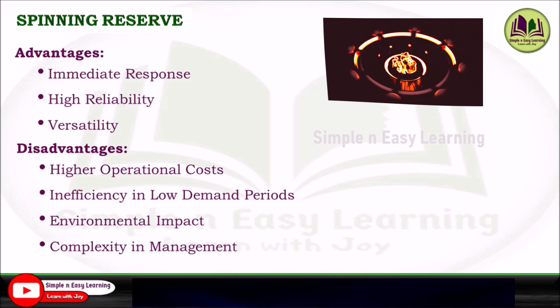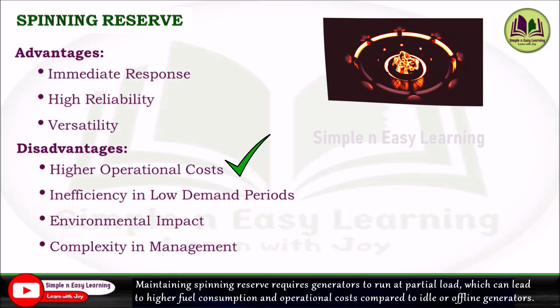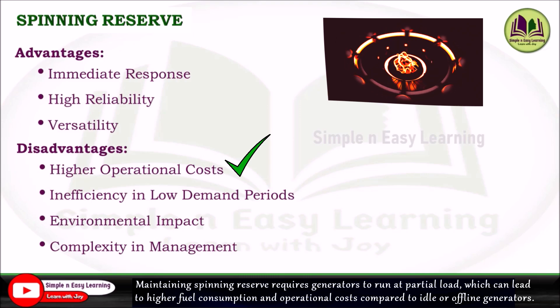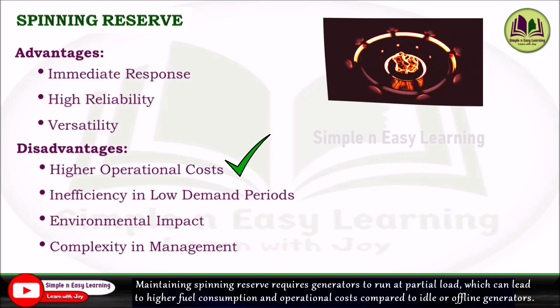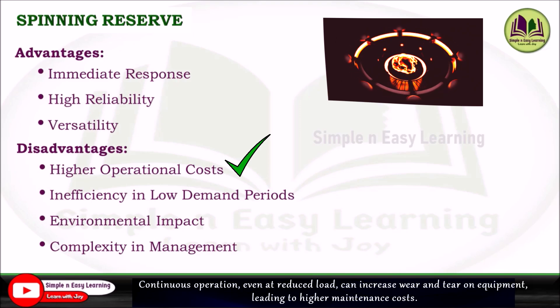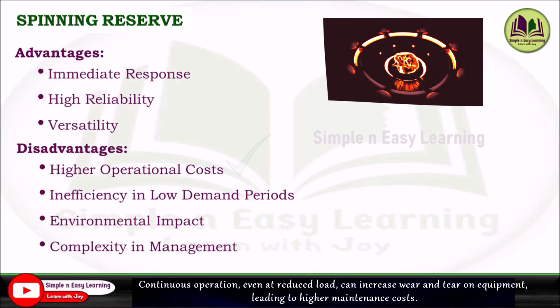Now we will see some disadvantages of spinning reserve. The first is higher operating cost. Maintaining spinning reserves requires generators to run at partial load, which can lead to higher fuel consumption and operating costs compared to idle or offline generators. Continuous operation, even at reduced load, can increase wear and tear on equipment, leading to higher maintenance costs.